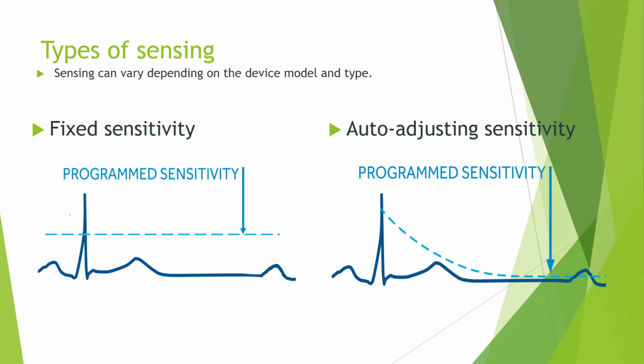It starts, for example, at the peak of the detection of programmed activity. For example, it starts at 8 millivolts of the R wave. After a fixed time, it will reduce it by, for example, 75%. After another fixed time, it will reduce it by 50%. And after another time, reduce it by another 25%, till it reaches the baseline. And once it thinks that it is getting closer to the next depolarization wave coming from the ventricle, it will increase back to the original amplitude. That's what we call auto-adjusting sensitivity.